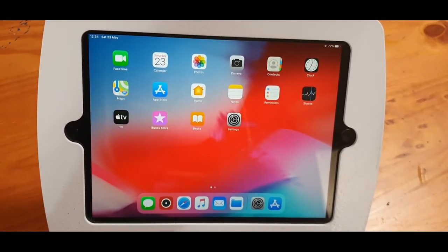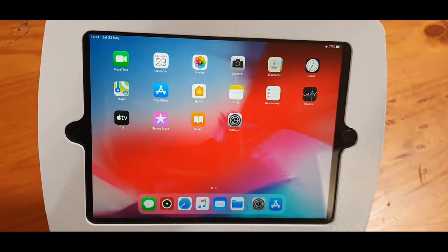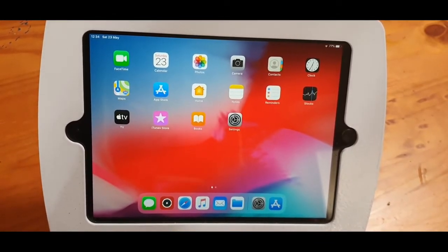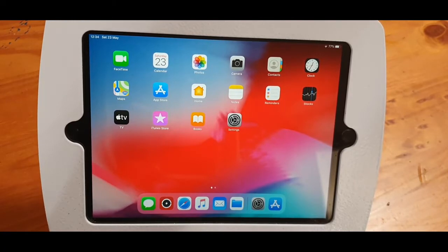We've got an iPad here on a desktop stand, which will be used in a guardhouse mainly for the Hik-Connect app, to be able to speak to an intruder on the perimeter. We're using bi-spectrum Hikvision cameras — the thermal and the color camera all in one. The color gives you visual verification and the thermal provides accurate triggers; line crossing and intrusion are the two VCA features we used.